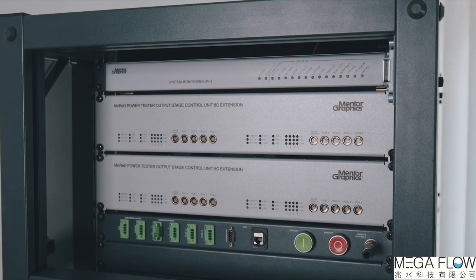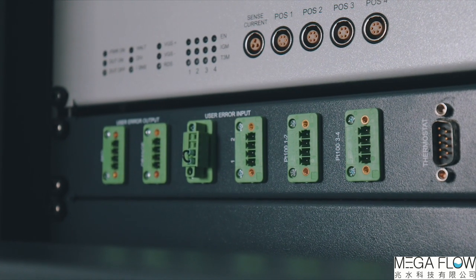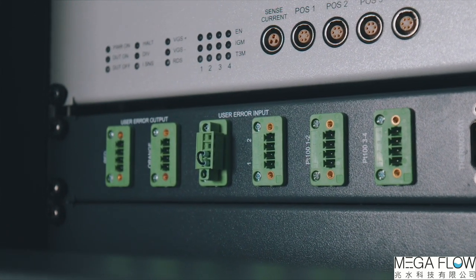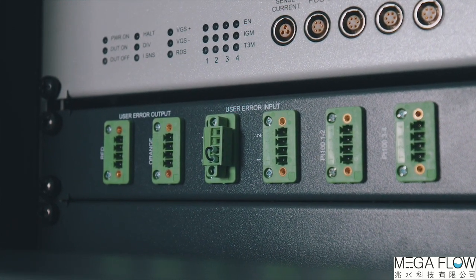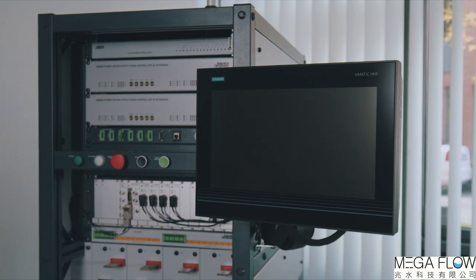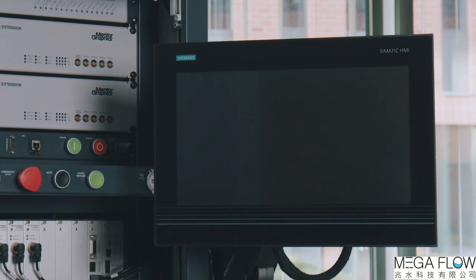automatic temperature sensitivity calibration. The high current operation, of course, requires dedicated safety sensors and mechanisms that allow autonomous operation without constant supervision and provide alarms or even shut down the power tester in case of critical safety events. There are dedicated safety sensor inputs available, so you can connect it to your measurement environment and set it up in the control software. The system has built-in control computer and provides easy-to-use touchscreen interface for easy operation. This covers the full workflow from the device definition to the actual RTH measurement or power cycling.